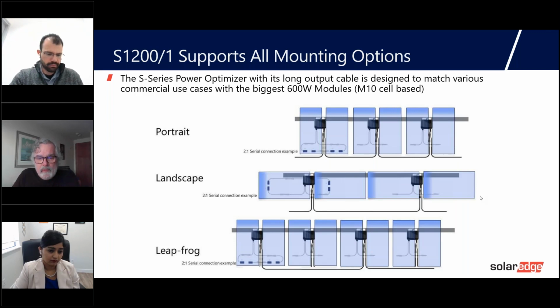And so this does a couple things. Like I said, it'll use up some of the extra wire that you might have to coil up and wire manage. It also allows you to go all the way up to one end, every other module, and then turn around and come back the other way, every other module. And it prevents you from having to run a long return wire from the far end of the module row. So that's one of the reasons it's pretty commonly done on single axis trackers. That way, both the positive and negative connectors for the string are at the same end. It also works out on a ballasted rooftop if you have fairly long rows that would support an entire string of modules.